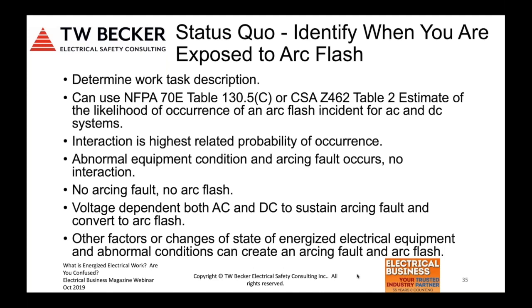So as far as the work tasks the qualified electrical worker performs, interaction is the highest related probability of occurrence. Abnormal equipment condition and arcing fault can occur with no interaction as well. No arcing fault, no arc flash. This is a voltage dependent hazard, both AC and DC, to sustain the arcing fault and convert it to an arc flash or create the arc flash. Other factors are change of state of the equipment and abnormal conditions that create an arcing fault and an arc flash.